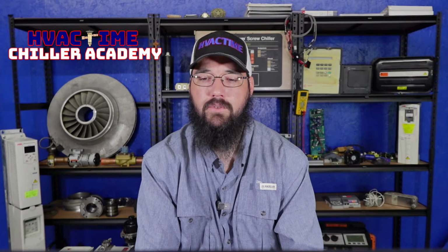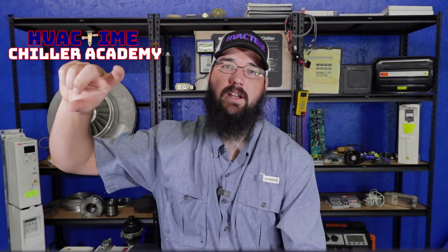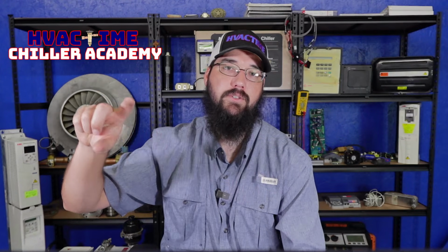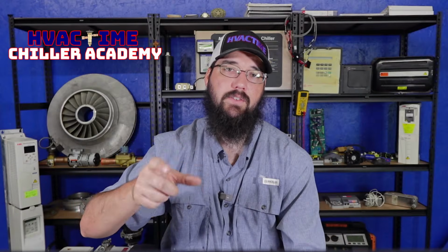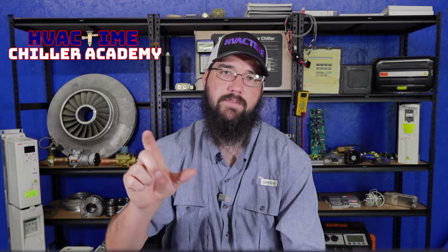See, 5 volt in, 2.5 volt out is half of the range transducer output in a nutshell. Yeah. Well, I mean, and that's if, now most transducers, to your point, Tom, how you doing, Tom? By the way, most transducers are fairly linear, meaning that they have a fairly straight line on a graph, but not all do. Some of them are non-linear, and so you'll have this kind of sliding scale range of how much the pressure fluctuation affects the VDC output. Now, again, the vast majority of them are fairly linear, like close enough to linear that you could call it a linear scale.